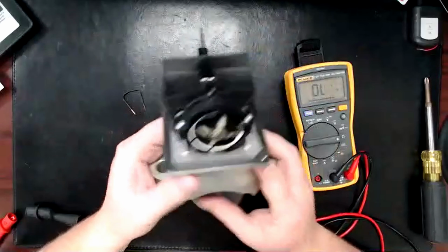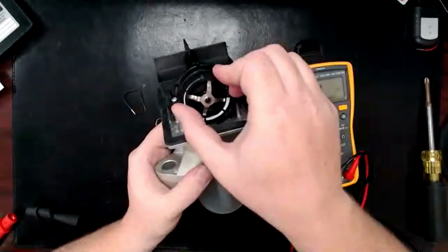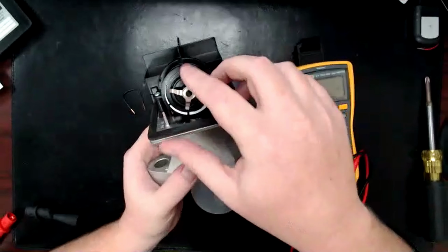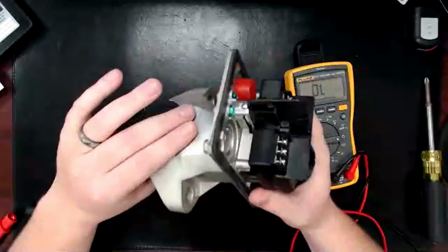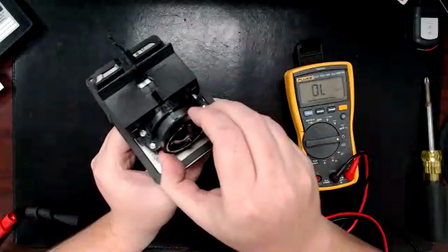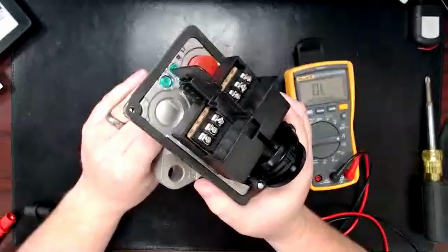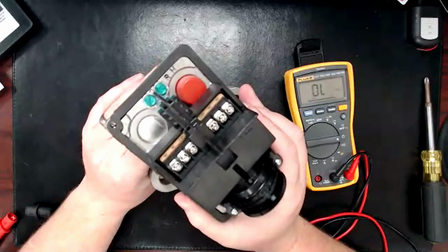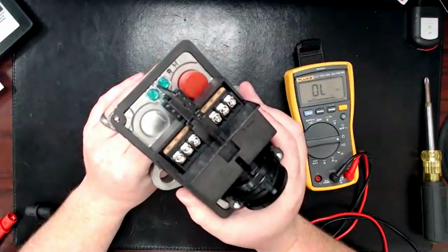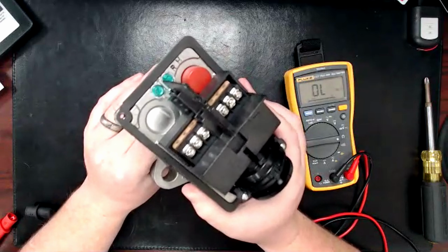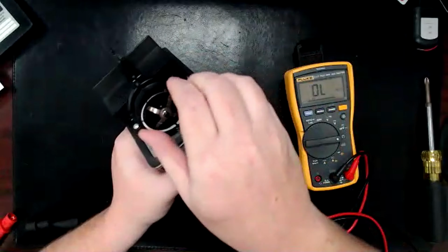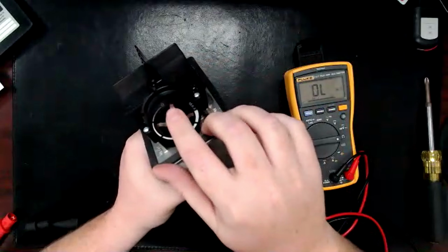And then down here on the bottom, this is actually how we adjust the time delay. So set it to 0 right now. There is no time delay. Whenever this paddle gets pushed, it immediately changes state. And then if I turn it a little bit and I hold it, there's a timer in there, and then it releases. And I don't know if you could hear that, but it just clicked, so it just released. And then you can crank it up quite a bit, all the way around to that max right there. So right now I have it on 0, so there's no delay.